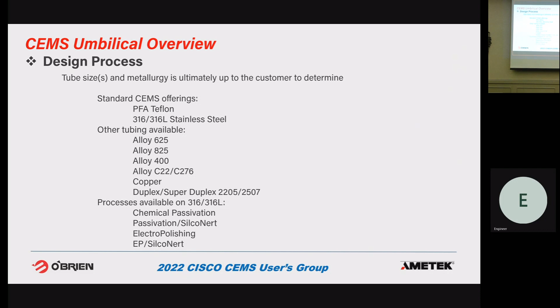So a couple recommendations when you're giving us information on what parameters we need to use to design your tubing bundle. The biggest thing that we see is that whatever maintain temperature you need, don't overinflate it. Because if your dew point is 180 and you're telling us you want to maintain 300, well, we can do it. In general, the higher it maintains, you get shorter circuit lengths, you draw more power, you need larger circuit breakers. We're having to use more expensive tracers in general.